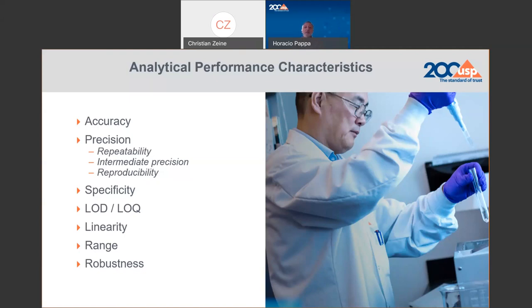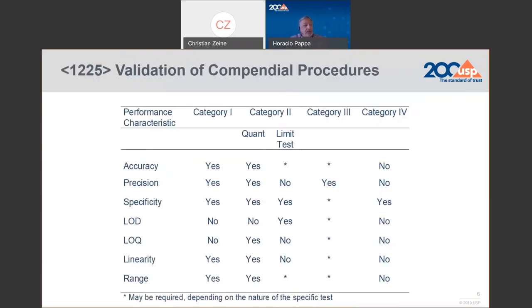In robustness, you use the fine-tuning of the method that has been developed, and this is where you will identify the system suitability parameters. This table is in ICH Q2 and in 1225, and is the basis of the current concept of validation, verification, and transfer. It defines what kind of experiments you have to do depending on the type of method you are trying to validate. Methods are divided in four categories: category one is when you are measuring the main component in a matrix; category two can be quantitative or limit test, and is for impurities—small components at low concentration.